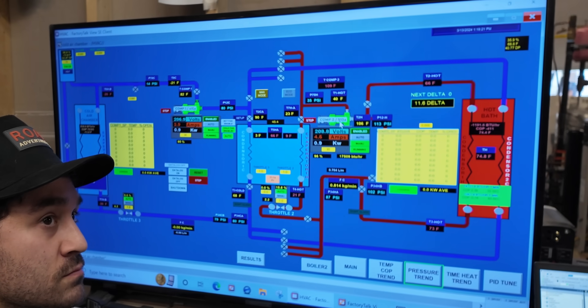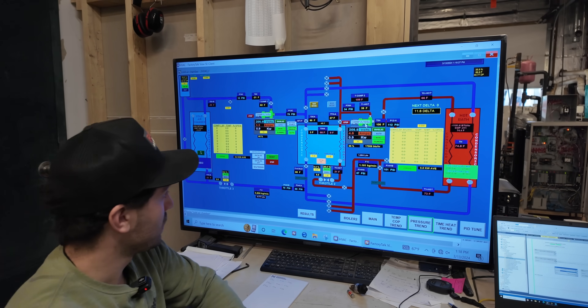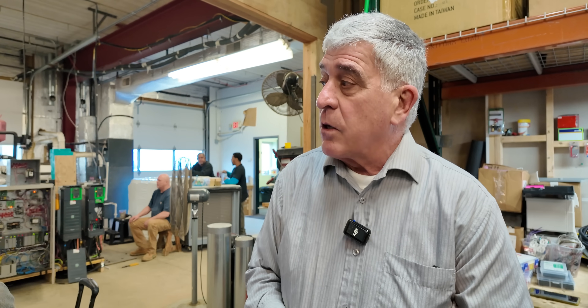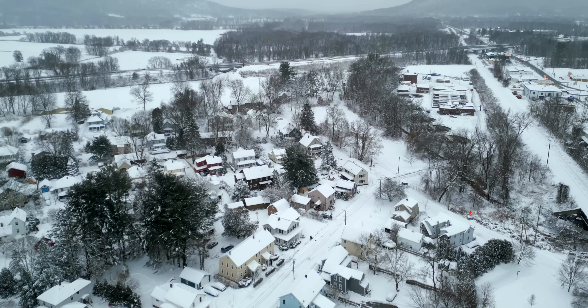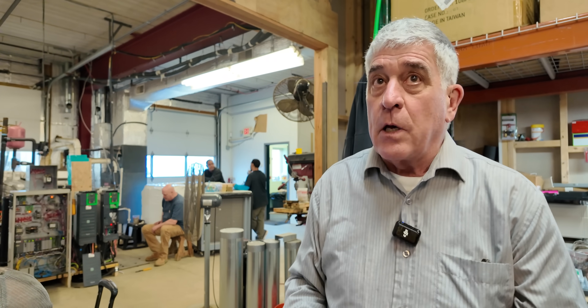"So this will always save you energy. If you're above a COP of two or so, it will most likely save you money as well. The other advantage of this particular system is when we're at low deltas, which is the majority of the heating season, which would be around 40 degrees, 30 degrees, that type of thing, our capacities are 200 to 300 percent. When it's normal heating temperatures here in New England, we're not doing 100 percent capacity. We're doing two or three. So our two-ton system is acting like a four or four and a half ton, even a five ton system at times, but it still doesn't use any more electricity."